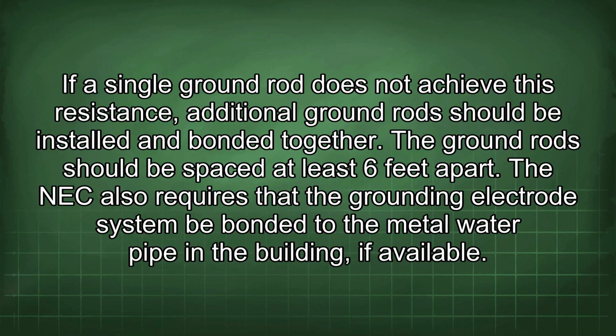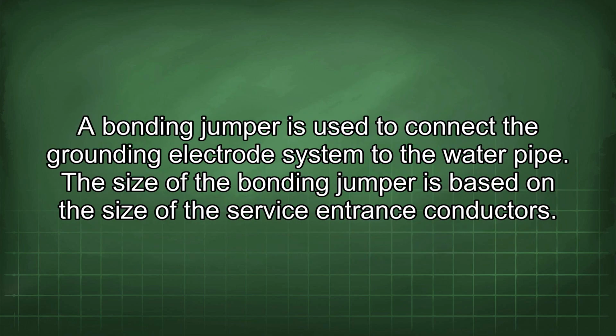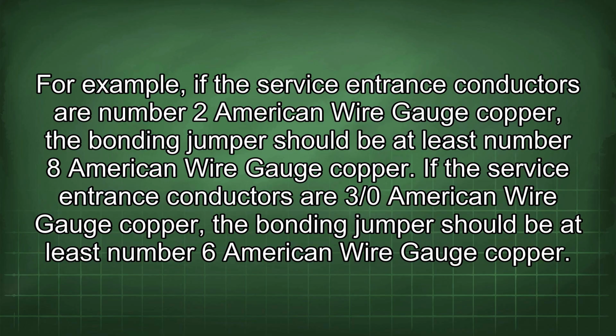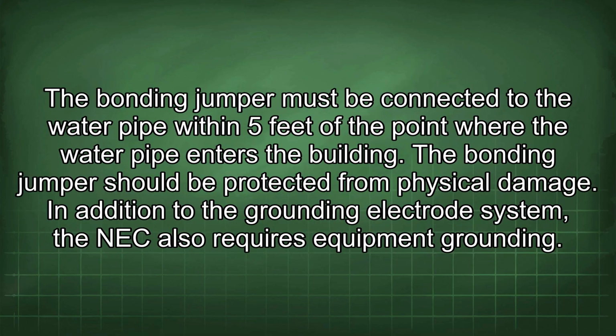The NEC also requires that the grounding electrode system be bonded to the metal water pipe in the building, if available. A bonding jumper is used to connect the grounding electrode system to the water pipe. The size of the bonding jumper is based on the size of the service entrance conductors. For example, if the service entrance conductors are number 2 American wire gauge copper, the bonding jumper should be at least number 8 American wire gauge copper. If the service entrance conductors are 3/0 American wire gauge copper, the bonding jumper should be at least number 6 American wire gauge copper. The bonding jumper must be connected to the water pipe within 5 feet of the point where the water pipe enters the building. The bonding jumper should be protected from physical damage.